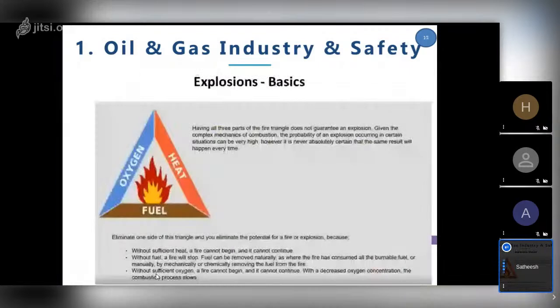Another important point: not all fuels have the same compressibility or flammability. For example, petrol has its own combustion index, diesel has its own index, and gas is something different. So the flammability of each fuel is different. Some can burn at very low temperatures - the heat can be so low, but combustion and explosion can still occur. Some gases allow a little more temperature increase before igniting. So flammability differs for different gases, and that matters when selecting your equipment or classifying an area - how critical it is based on the nature of the gas and its flammability limits.